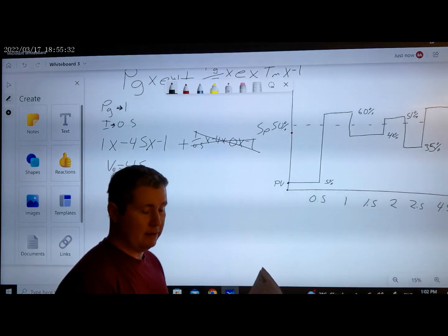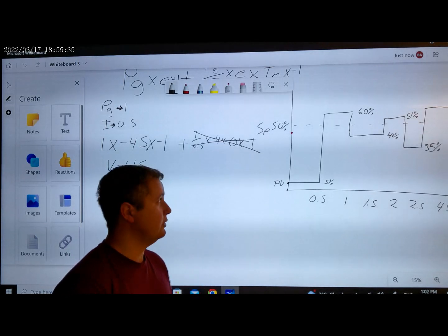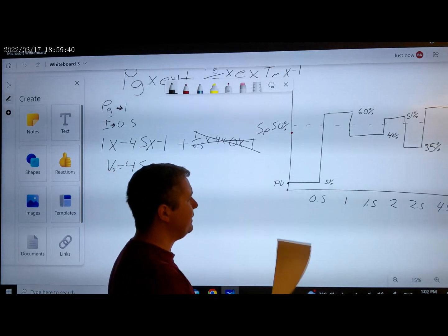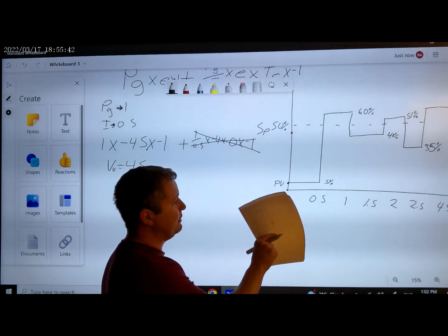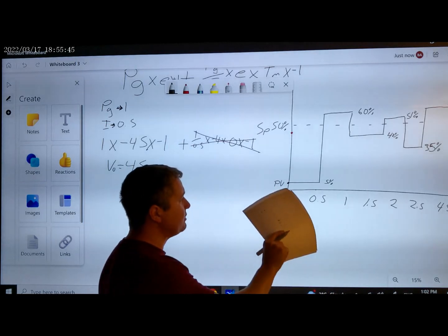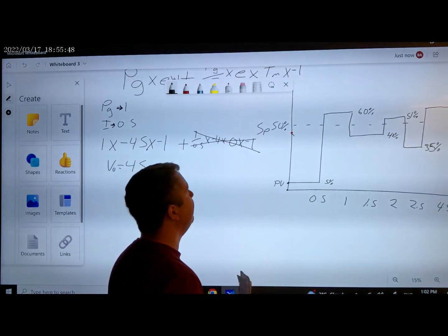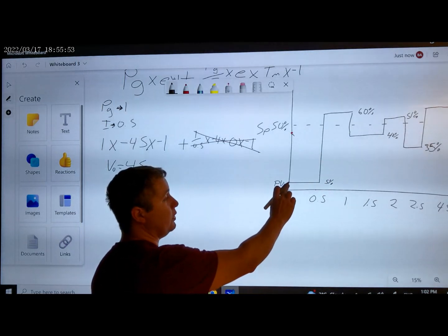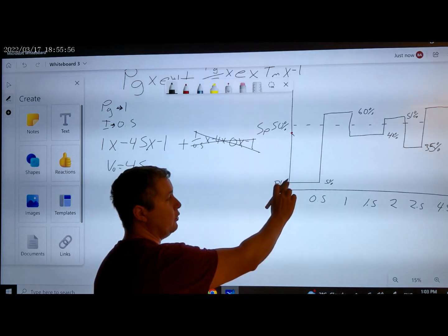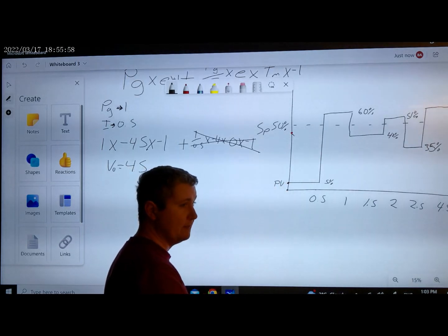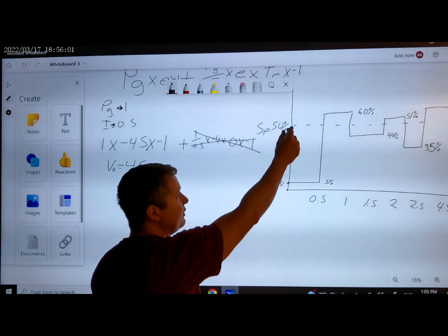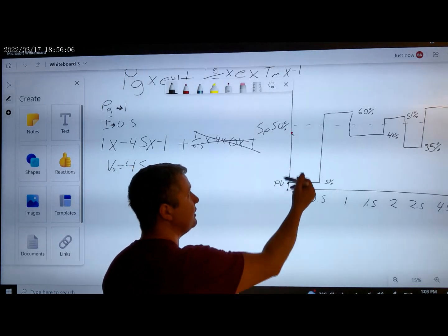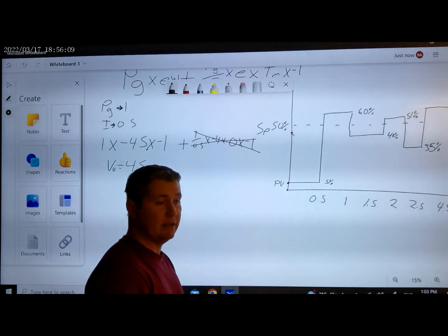But this is in order to calculate what the integral is going to do. So what we need to do, the integral and proportional. So we calculated out exactly what's going to happen as soon as we turn our controller on. It's going to jump to 45% output because of our proportional gain and our process variable is at 5%, right? Because there's a negative 45 error and we're in reverse acting, it's going to give 45% output.